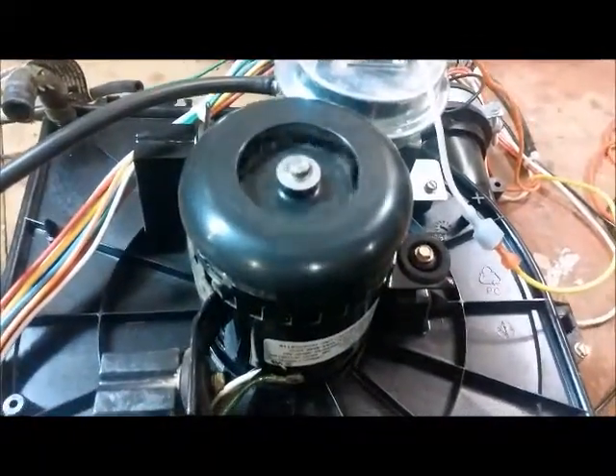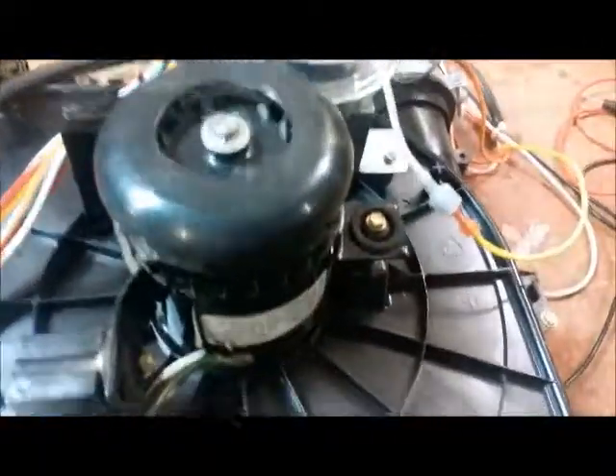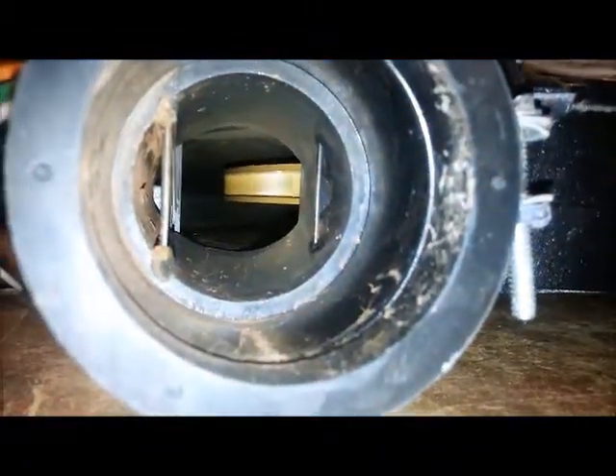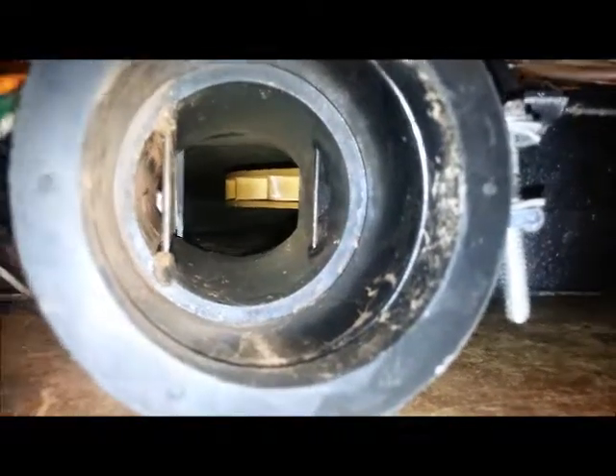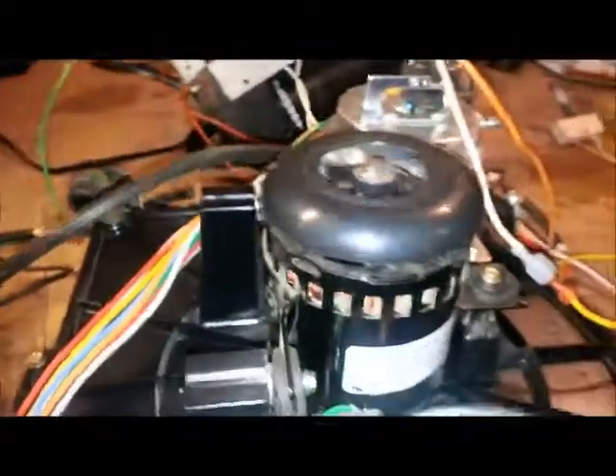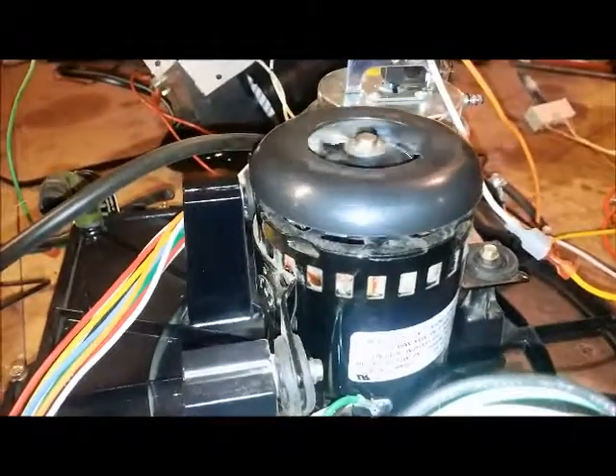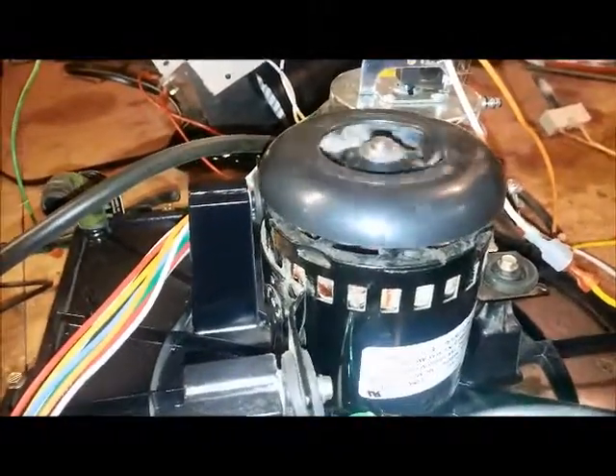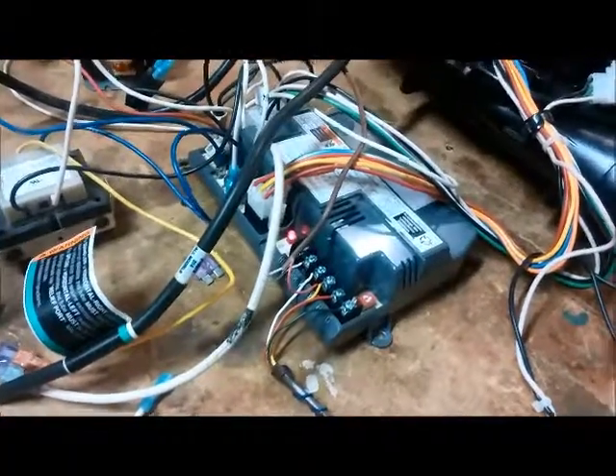You know, this motor should spin freely like that. Sometimes the inducer wheel, the wheel that's spinning in there, will come separated from the shaft on this particular model. And if that wheel is separated, that will not spin more than a couple times. Most of these newer furnaces are definitely going to need a ground. So as you can see, everything looks normal. Steady on.